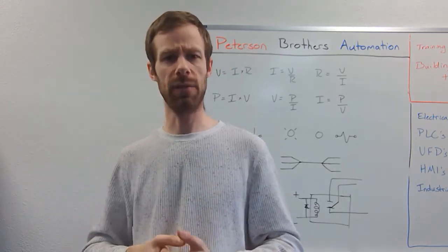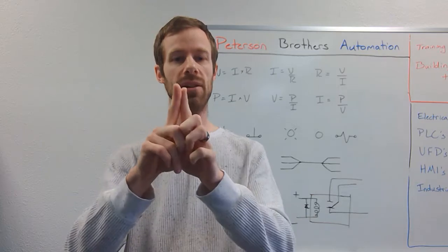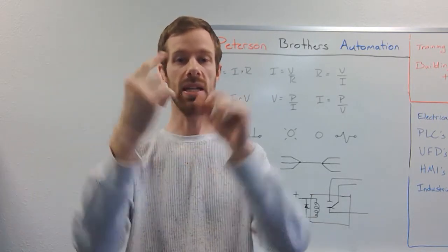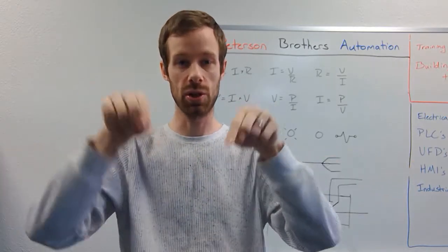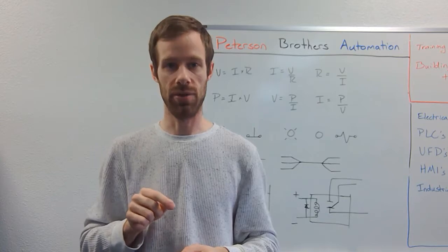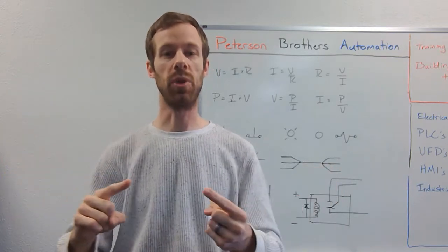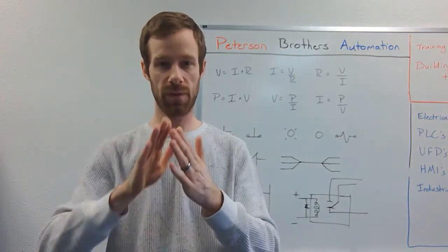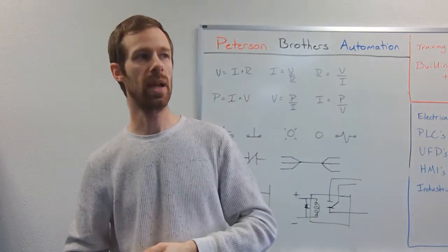That would probably be a difference between whether you see 2 black wires or 3 black wires under a wire nut, which means power is coming in and then it's going out to 2 different load devices. Or you see 3 white wires under the wire nut, which means the power is returning to neutral from 2 of them and going back out through 1 wire back off to your panel.